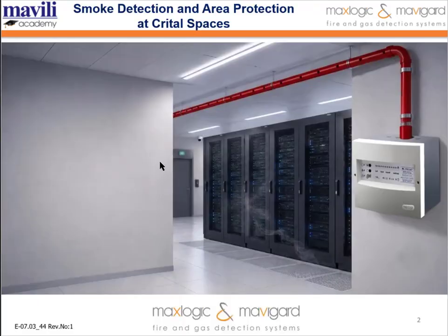So let's begin. This week's webinar, titled Smoke Detection and Area Protection in Critical Areas, will address the correct detection approach in areas with a high risk of fire or where operational continuity is of paramount importance in the event of a fire. Early detection of smoke in critical areas such as data centers, electrical rooms, panel rooms, archives, or warehouses, and other examples, technical areas and similar locations, is crucial for life safety, critical equipment protection, and also operational continuity.